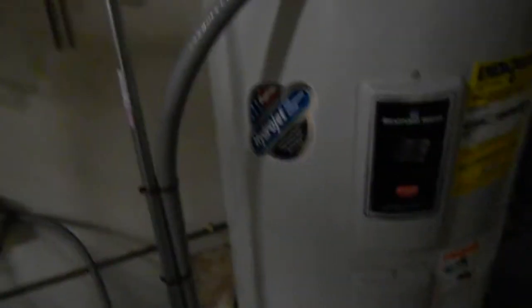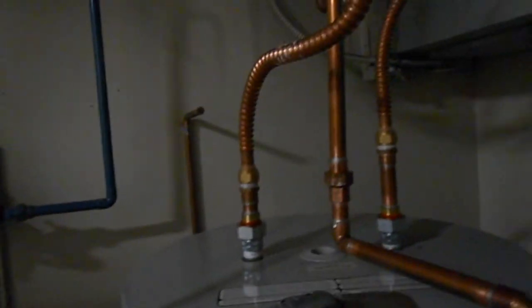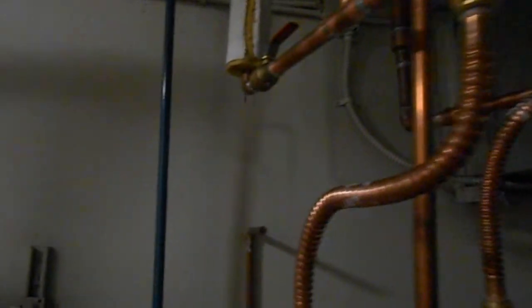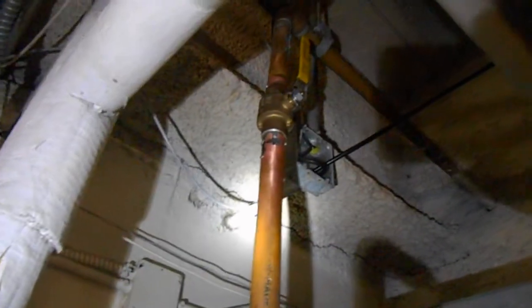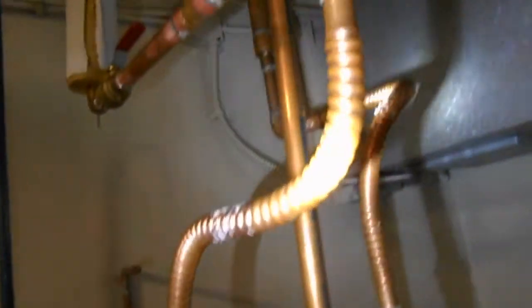Okay guys, we're all done. Sorry I didn't get any action shots in there — thought I was going to but it really wasn't a great place to set the camera. They just shipped me my hat camera so I should have that for the next video. Anyway, we've got our inch-and-a-quarter cold water shutoff up there installed. Got a little sloppy with the bottom joint but it's sealed. We've got our full-flow water flex going down to a dielectric union on both sides, hot water flex, isolation valve, and then I teed off a little hot water hose bib here with a union on it right there so you can take the heater out if you need to.